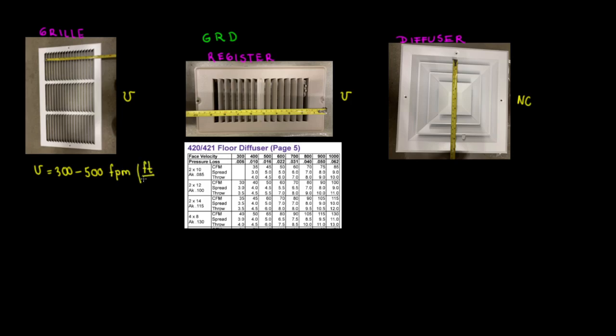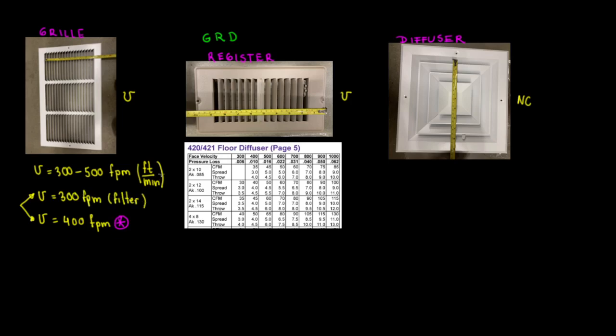To make it a standard for design, we're going to size grills based on a velocity of 400 FPM, which is the average of 300 and 500. 400 FPM would be optimum. However, if you have this return with a filter, we're going to aim for a velocity of 300 FPM instead.